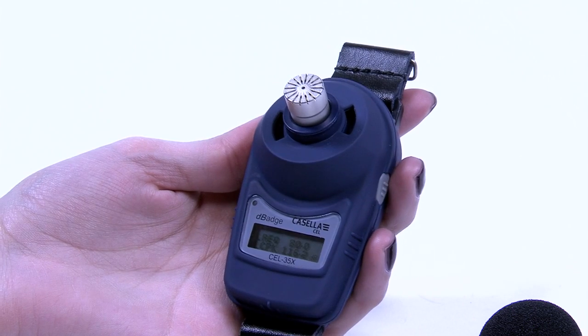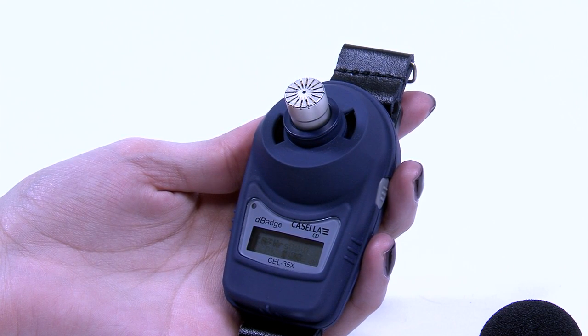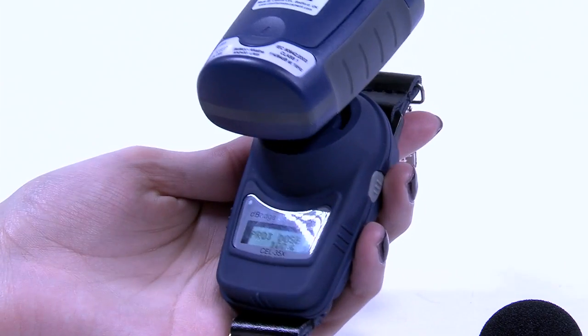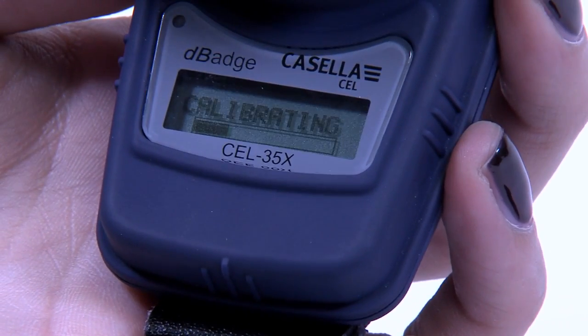Calibration can easily be achieved on-site, ensuring that measurements are taken without delay or interruption. Place the Casella 120 series calibrator over the microphone and the dBadge will do the rest with its auto-calibration feature.